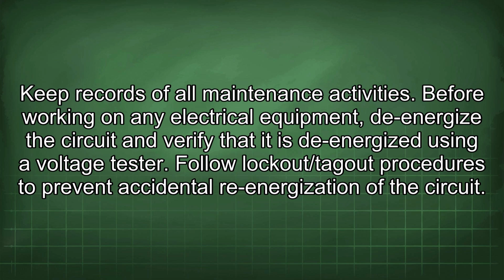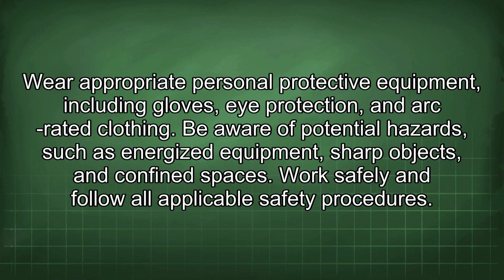Before working on any electrical equipment, de-energize the circuit and verify that it is de-energized using a voltage tester. Follow lockout/tagout procedures to prevent accidental re-energization of the circuit. Wear appropriate personal protective equipment, including gloves, eye protection, and arc-rated clothing.